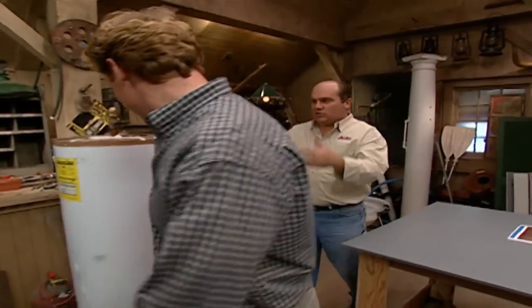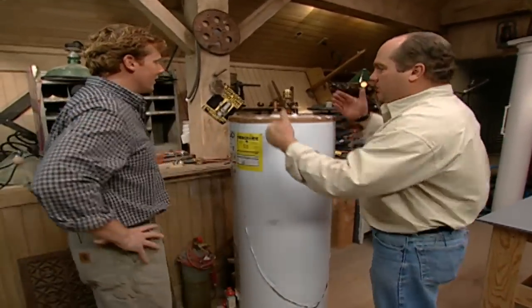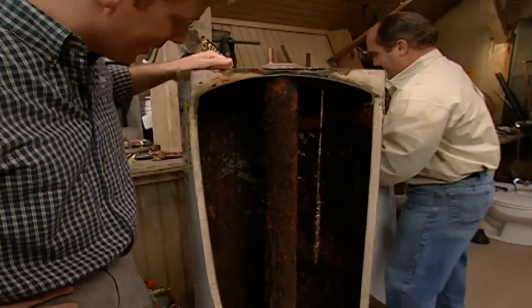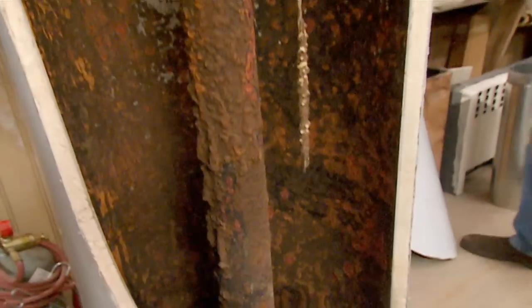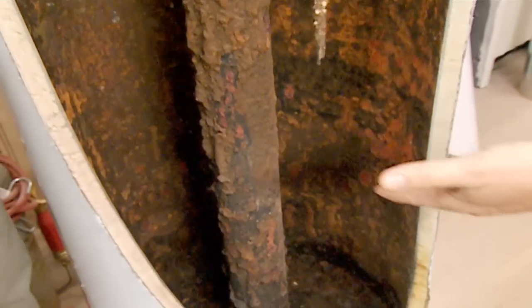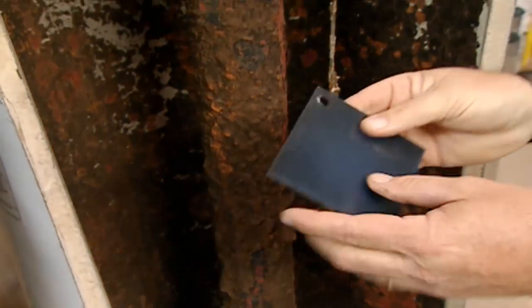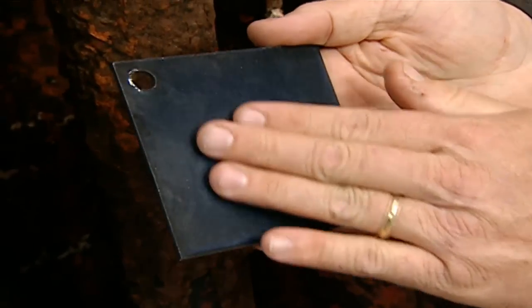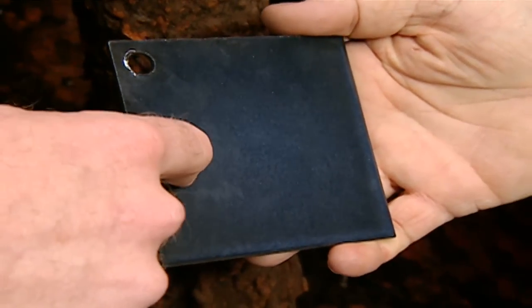So this is the actual water heater from that house. I took a saw and I cut it apart. Oh, Richard, this is horrific. That is horrible looking. What happened? Well, this is a glass-lined water heater, glass-lined steel, actually. The tank itself is made out of steel on this side, and on this side is this enamel coating. Oh, that's the glass they're talking about. That actually just kind of wraps around in here over the steel? That's right.